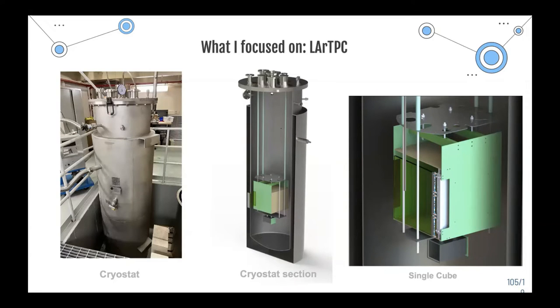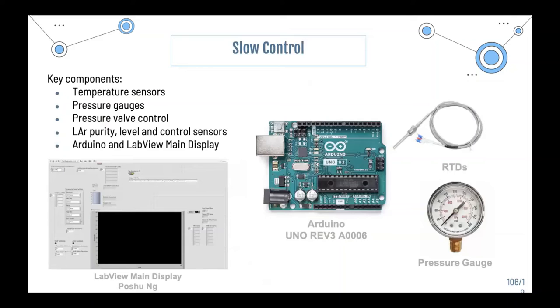We're using liquid argon, but how do we keep liquid argon liquid at a given temperature and pressure? We use slow controls. Slow controls are devices able to monitor and regulate the temperature, pressure, and liquid level of liquid argon. Not only do they help keep the pressure and level of liquid argon steady, but they are also implemented with a negative feedback loop able to maintain liquid argon pressure and temperature stable.